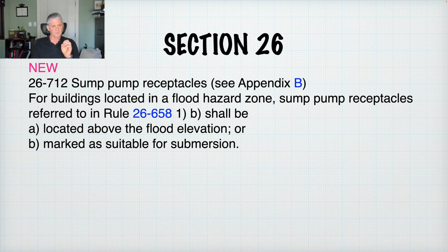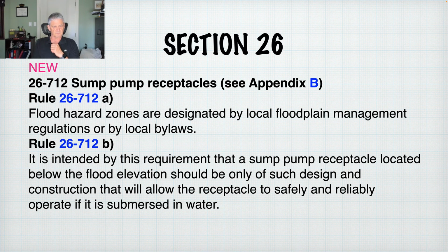New, and this goes back to the flood hazard zone. So if a sump pump is for a building in a flood hazard zone, the receptacles must be located above the flood elevation or marked for suitable for submersion. And more on the flood hazard zones.